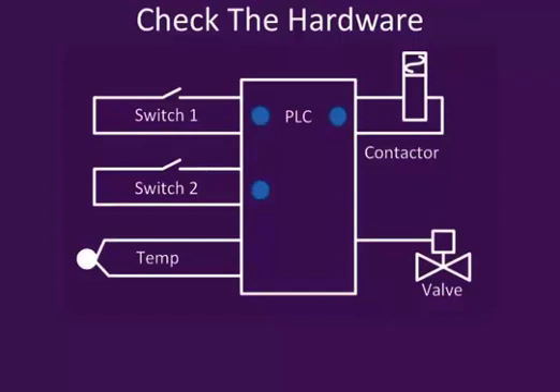With the outputs, the contact outputs, firstly you go and check that it's all right to switch stuff on, because there's a chance you'll be turning stuff on once you start clicking the outputs. Then you turn it on in the software. If everything's okay, click, the correct contactor should come on.